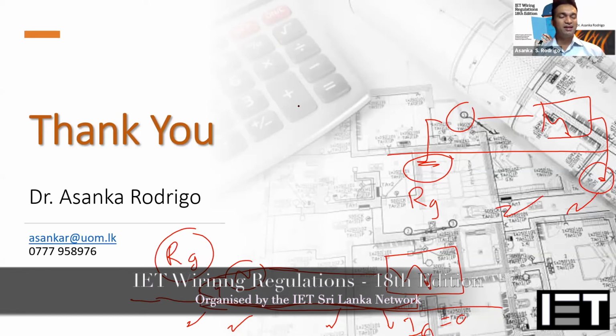And then the people called the ES, and the ES confirmed that yes, they have put two different earths. But I called the engineer and checked whether they are using this type of arrangement. He said, no, sir, we are not using. I already asked these people to put the common earthing, don't use different earthing. Maybe this is a new ES who came from somewhere in the distribution region and he will use something else. I will ask him to correct it. We have a situation like that. Fortunately, I told the Colombo City engineer, and he confirmed that it is not happening.